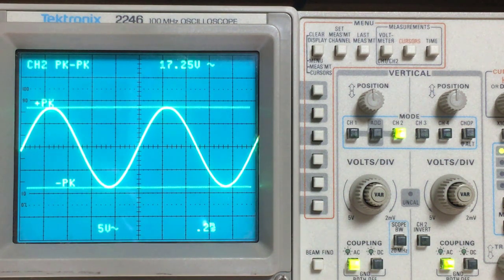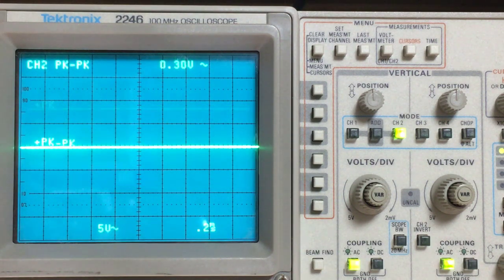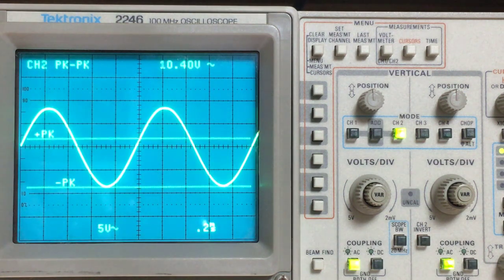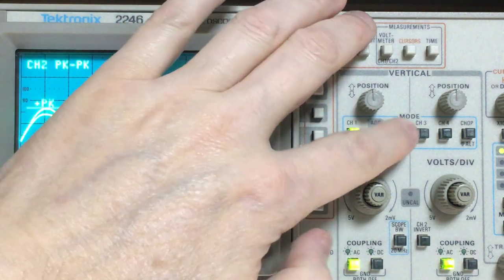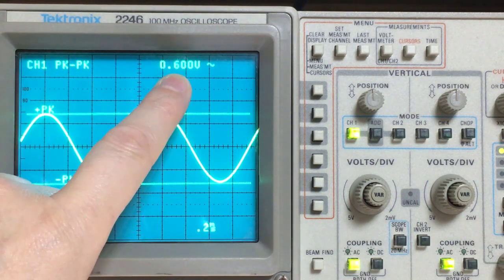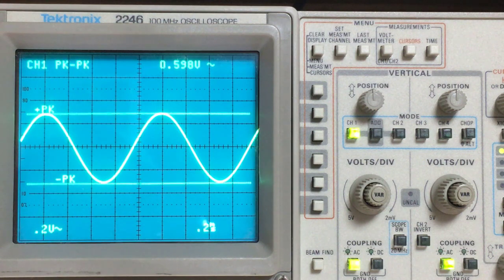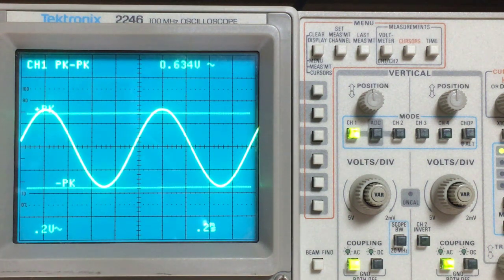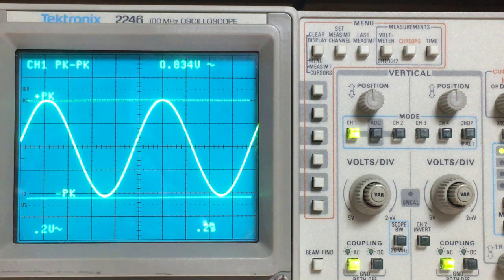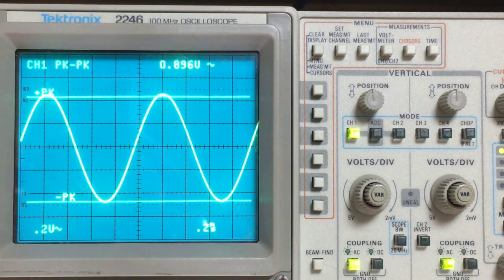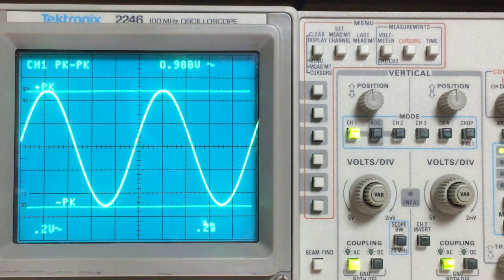Now we're going to move our input over. Instead of going A to C, we're going to move it to go A to B at this point. Let's go back to channel 1 here. Notice we're way down here. It's a different reflected impedance because you're feeding a different set of taps on this transformer, so you have to readjust the input. Always make sure to do this when you change input connections, always come back along.